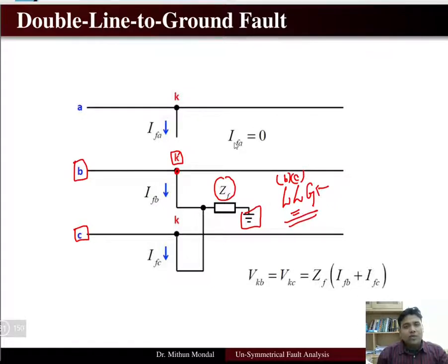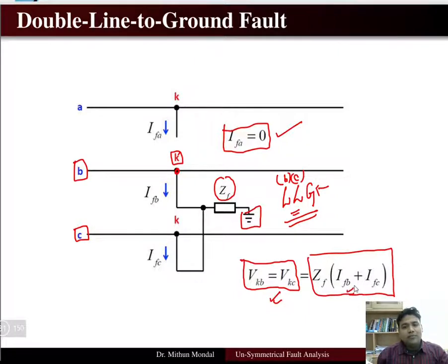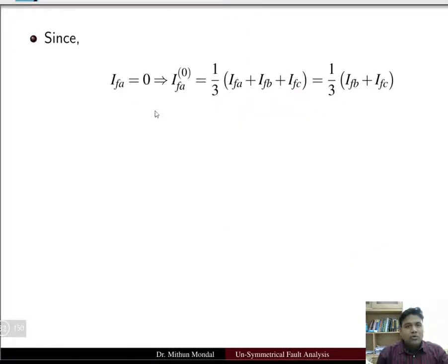Since phase a is not associated with the fault, the current in phase a due to the fault is zero. The voltages of the fault bus k in phase b and c are equal, which is equal to Zf times the sum of the current in phase b and phase c. This is in accordance with KVL — the voltage drop in the bus, taking into account the sign convention for the current.